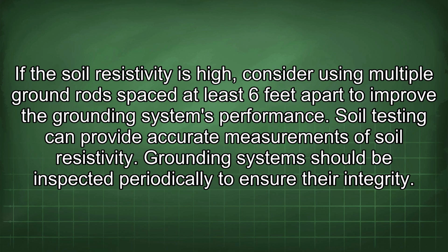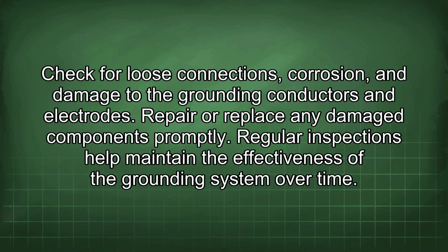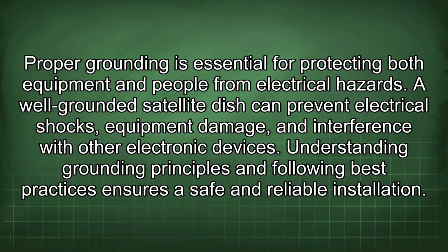Grounding systems should be inspected periodically to ensure their integrity. Check for loose connections, corrosion, and damage to the grounding conductors and electrodes. Repair or replace any damaged components promptly. Regular inspections help maintain the effectiveness of the grounding system over time. Proper grounding is essential for protecting both equipment and people from electrical hazards. A well-grounded satellite dish can prevent electrical shocks, equipment damage, and interference with other electronic devices. Understanding grounding principles and following best practices ensures a safe and reliable installation.